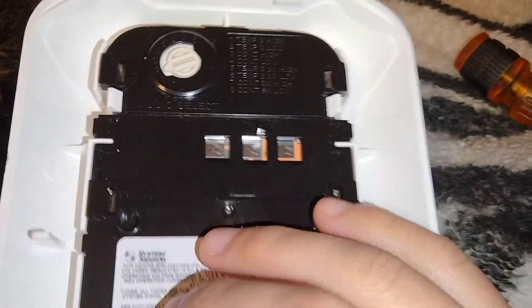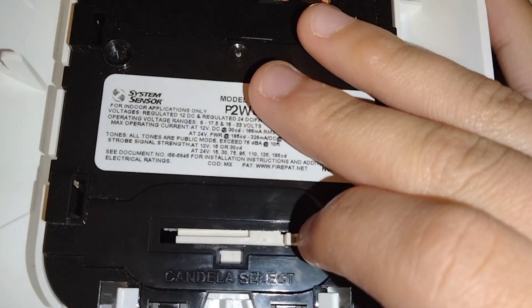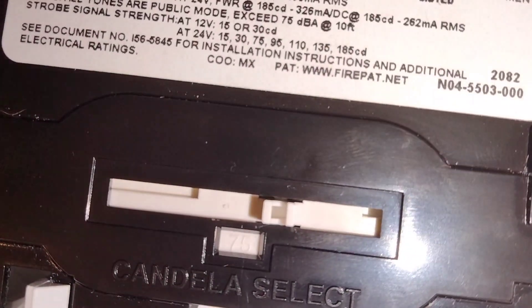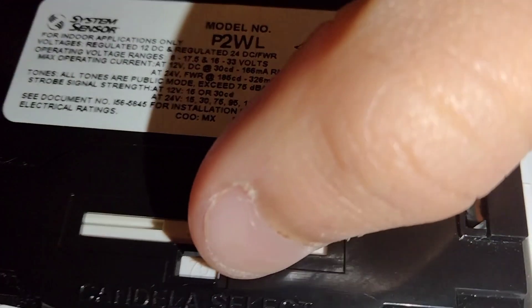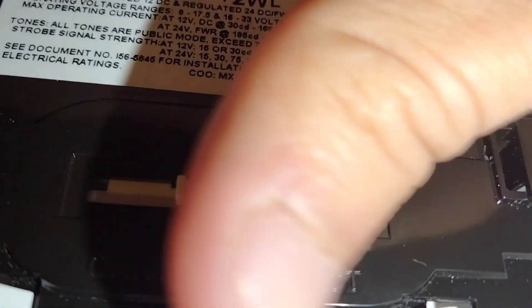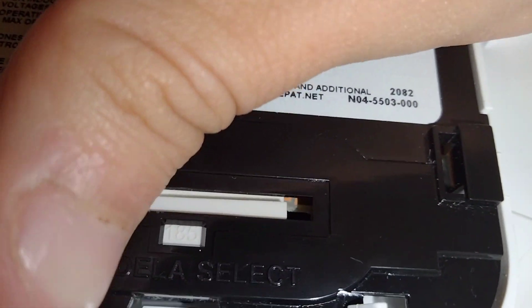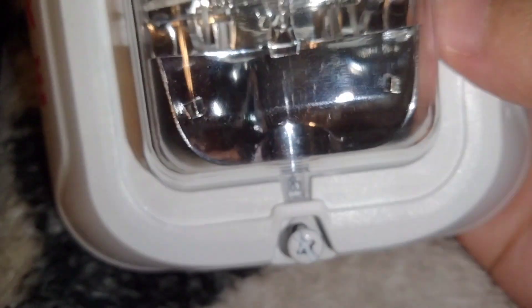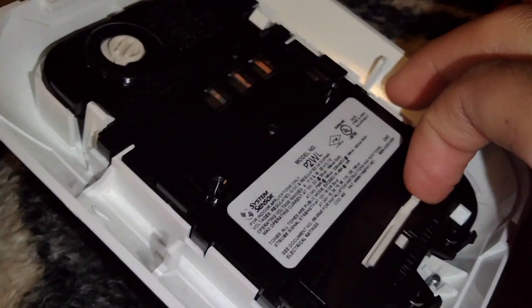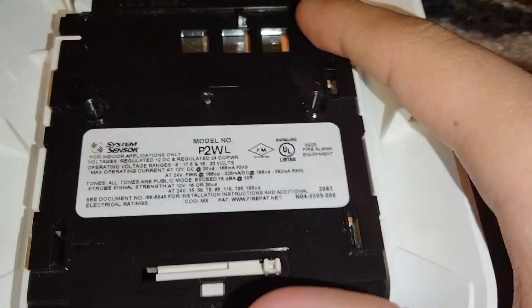Speaking of candela — this right here is your candela switch. All you have to do is slide it and it goes up to 185. It shows you the values down here: 75, then 95, then 110, 135, and 185, which is also listed below so an inspector can verify it meets requirements. I'm not sure 185 meets code unless it's for a specific application like an ADA requirement, so I left it at 15.